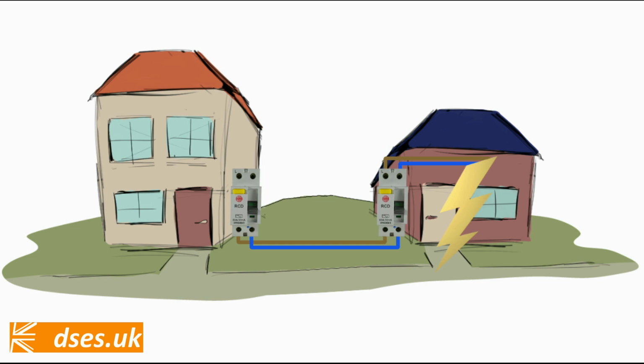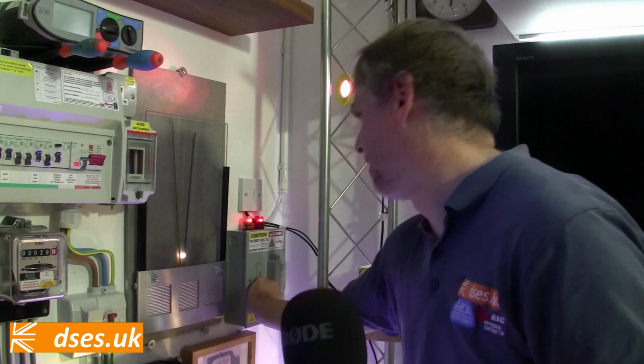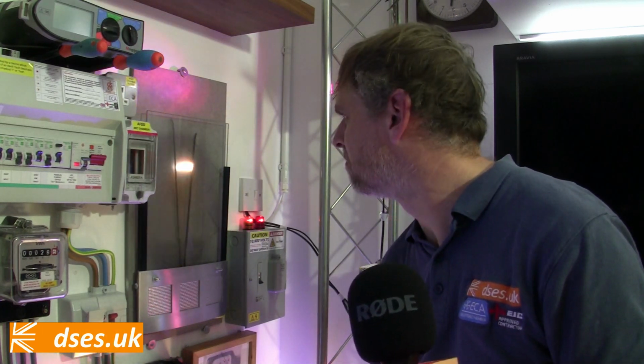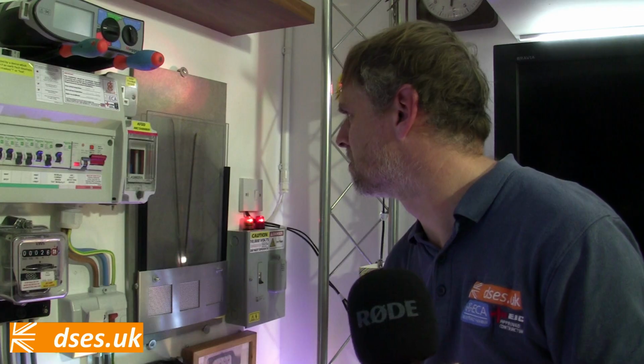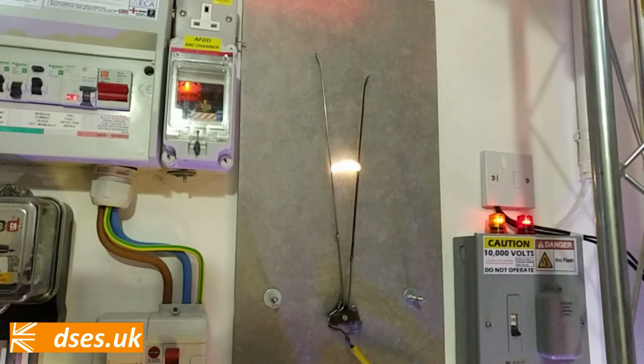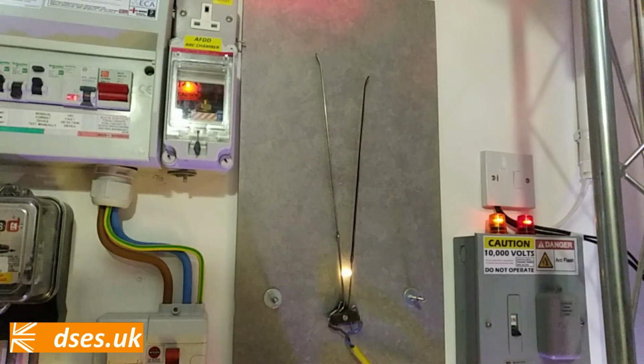You're not meeting the requirements for selectivity if you can trip a device that's not local to the circuit it's protecting, such as if you're working on the outbuilding and have no access to the house. Anyway, that's by the by. I only mention it here in case some smart ass brings it up in the comments. My AFDDs are only monitoring the distribution wiring for the most part. With the appliances, anything on the output side of a transformer, opto-isolator or whatever is invisible to the AFDD.